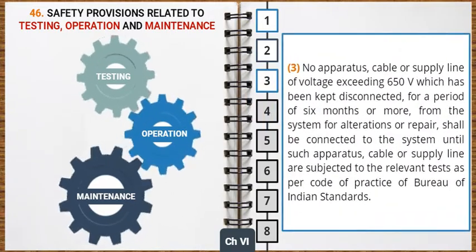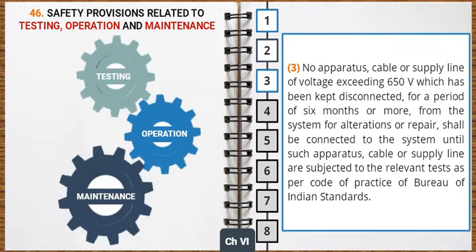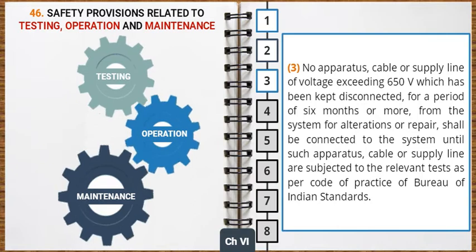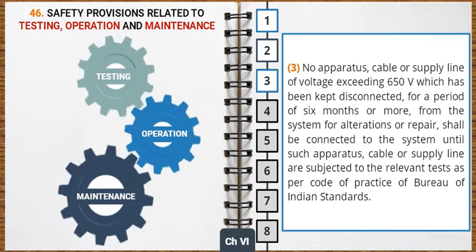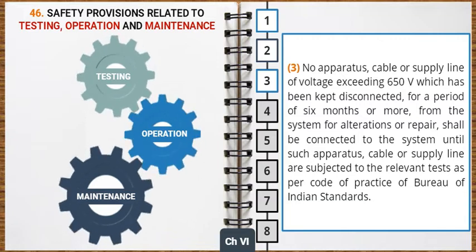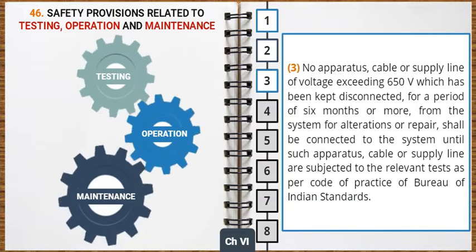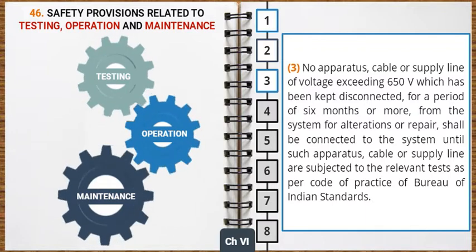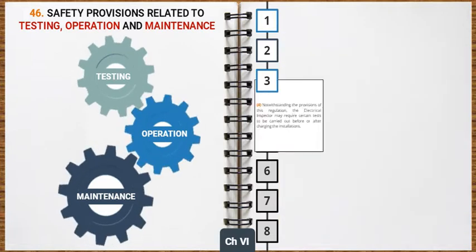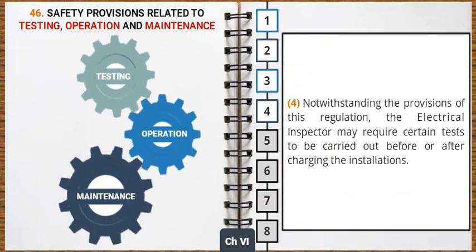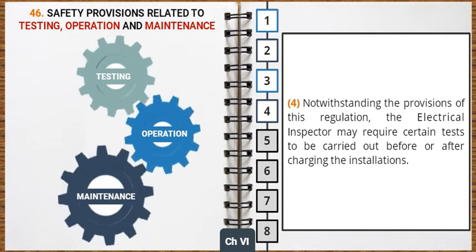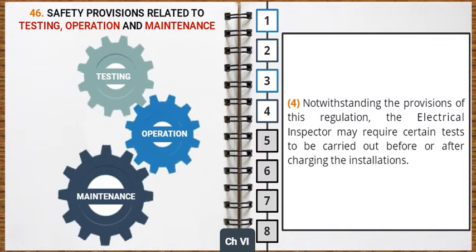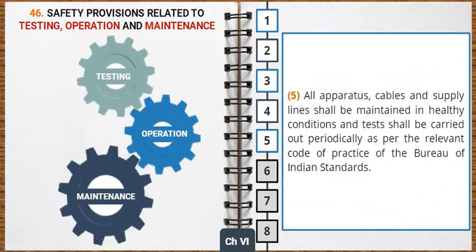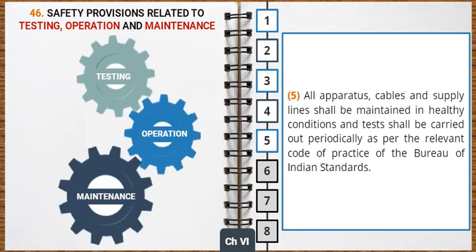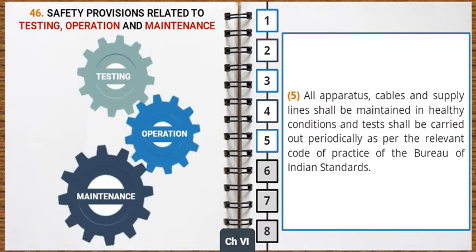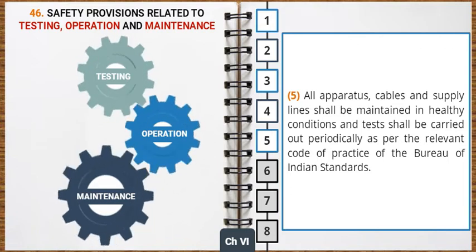No apparatus, cable or supply line of voltage exceeding 650 volt which has been kept disconnected for a period of 6 months or more from the system for alterations or repair shall be connected to the system until such apparatus, cable or supply line are subjected to the relevant tests as per Code of Practice of Bureau of Indian Standards. Notwithstanding the provisions of this regulation, the Electrical Inspector may require certain tests to be carried out before or after charging the installations. All apparatus, cables and supply lines shall be maintained in healthy conditions and tests shall be carried out periodically as per the relevant Code of Practice of the Bureau of Indian Standards.